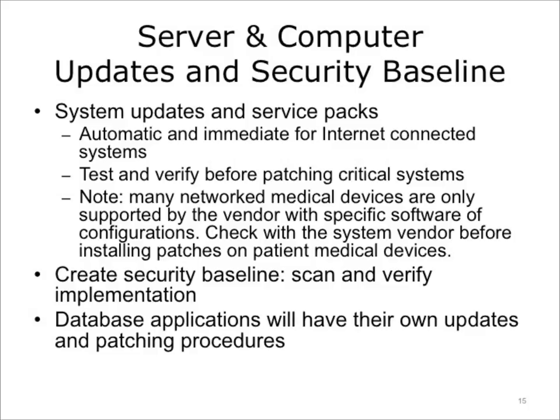Note that specialized medical equipment may have its own operating system, applications, and configuration. If the underlying operating system is vulnerable to an attack, do not immediately assume that a patch should be deployed. Some of these systems have only been certified or are only supported in specific configurations. Check with the system vendor before applying any patches or fixes in this environment, but during the vulnerable period, try to implement specific monitoring for attacks directed toward the newly discovered vulnerability.